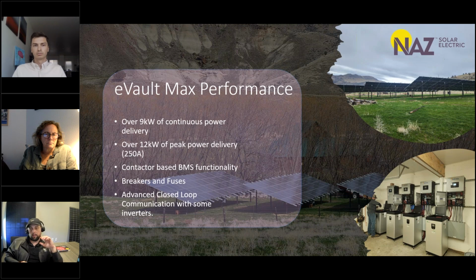Probably the most important aspect is the ability to do advanced closed-loop communications to a number of inverters on the market. That's very important when designing a system with lithium batteries, especially when it's a brand new solution or project. It's super important to have a relationship between the batteries and the inverter system—they need to communicate, providing current, voltage, and state of charge to the inverter, and regulating that charge accurately and quickly.